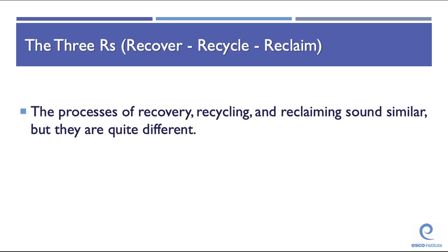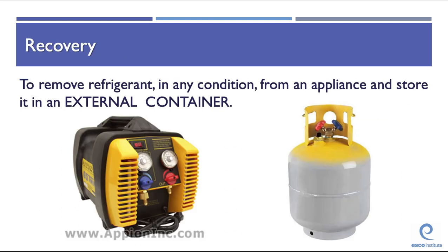The 3 R's that are going to be discussed are the processes of recovery, recycling, and reclaiming. Okay, these sound similar, but they're in fact quite different. Recovery is to remove refrigerant in any condition from an appliance and store it in an external container.